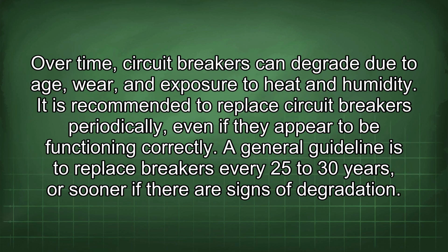Over time, circuit breakers can degrade due to age, wear, and exposure to heat and humidity. It is recommended to replace circuit breakers periodically, even if they appear to be functioning correctly. A general guideline is to replace breakers every 25 to 30 years, or sooner if there are signs of degradation.